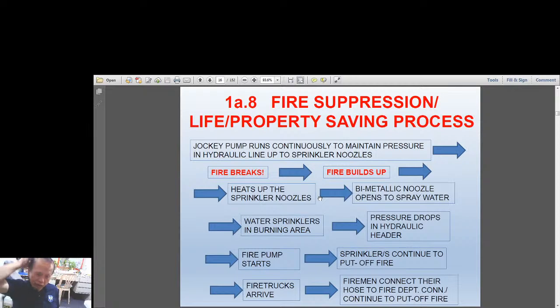The moment it sprinkles, pressure drops, then the sensor in the system will determine this, so automatically the fire pump will run, and of course the fire pump will continuously supply the fire water. Even if more sprinklers operate, the fire pump should be able to deliver the fire water, until of course fire trucks arrive and your firemen help put out the fire. The fire pump still operates even after the firemen arrive, until they are able to contain the fire, and that's the time they will maybe stop the fire pump, once the fire is under control. And the firemen will connect their hoses to the Siamese twin, or the fire department connection, in front of the building.